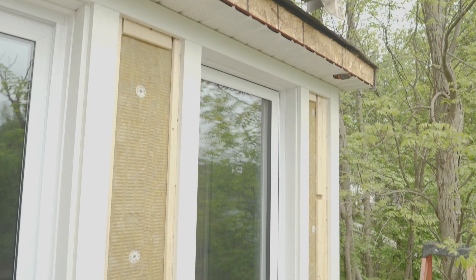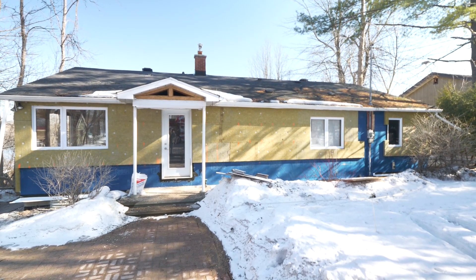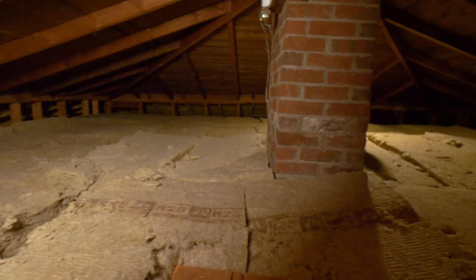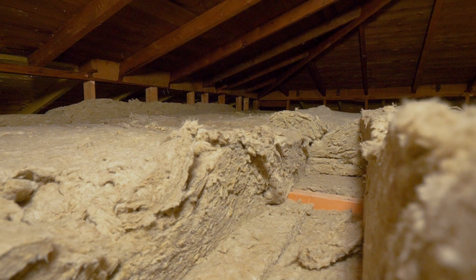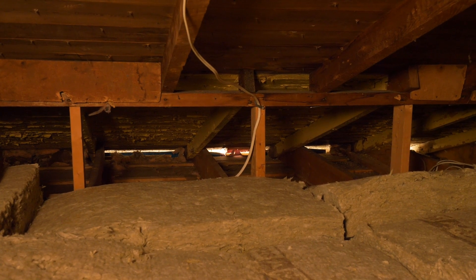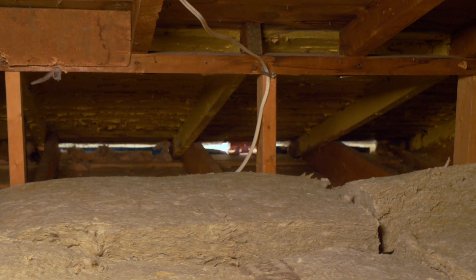We're replacing all windows with ENERGY STAR certified triple-glazed windows and upgrading all doors — though the front door will change location in phase two. The hot water system is upgraded to an air source heat pump. The roof will be rebuilt in phase two, but in phase one we increased attic insulation from R25 by installing two layers of R28 Comfort Bat at 24 inches on center, laid flat and overlapped in the current attic. This insulation will be reused in the scissor trusses for the cathedral ceiling in phase two. Around the eaves perimeter, blown-in loose fiberglass of about 4 to 10 inches will give approximately R30.